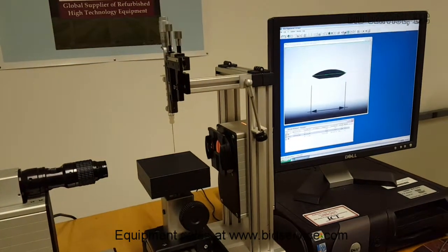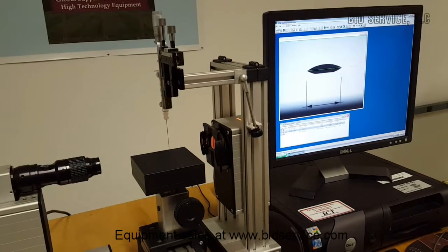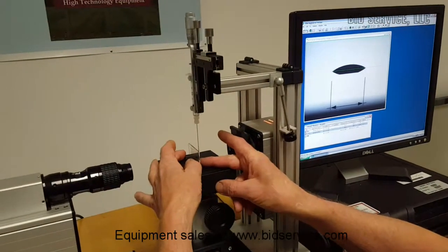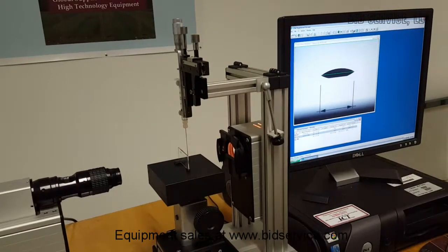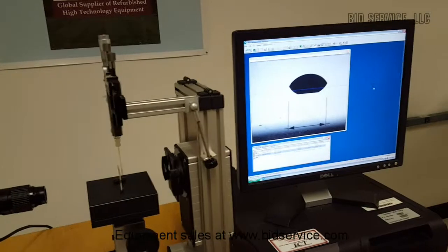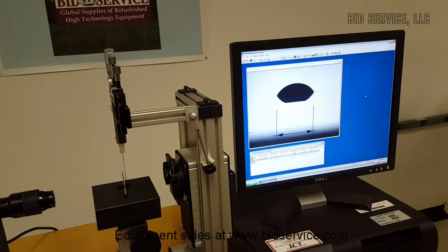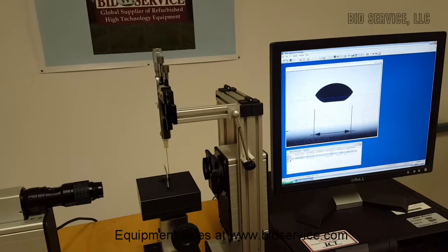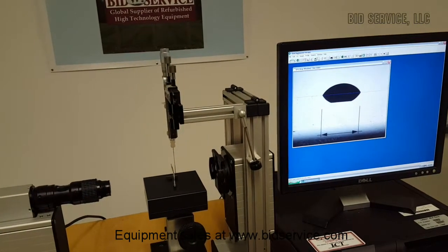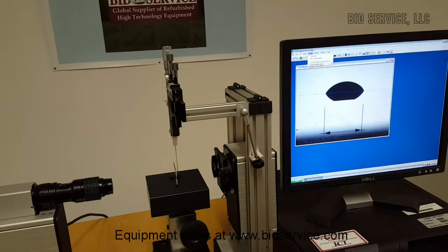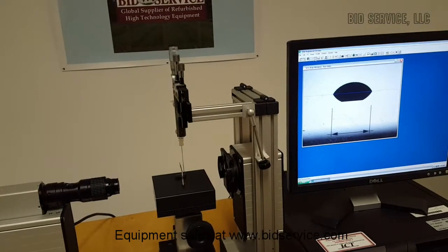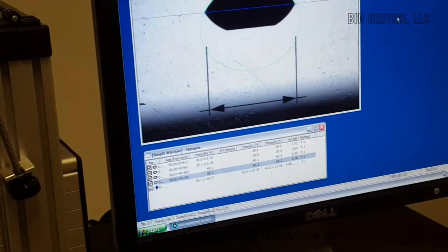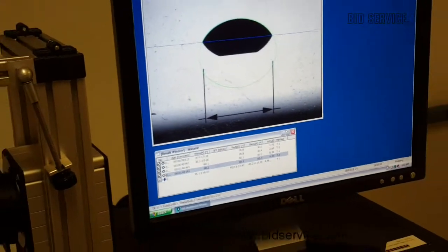Now what we'll do is I'll just freeze that image for a minute, and I'll move this first one. Put in the second one here, approximately where the other one was. And now we will reset our, oh, there it is. Okay, we'll move this right here. Make sure we're in focus. And establish our new baseline. One moment. Display our data. Wow, 60.2, and this is exactly 60 degrees. So that's definitely a good one too.